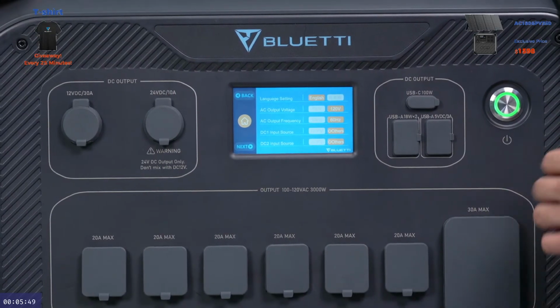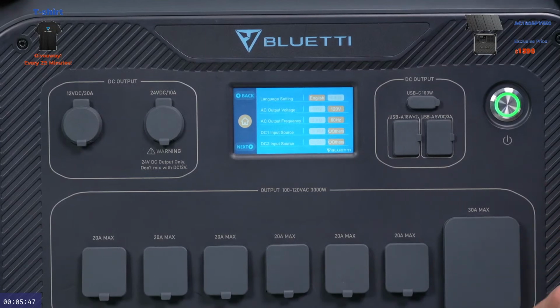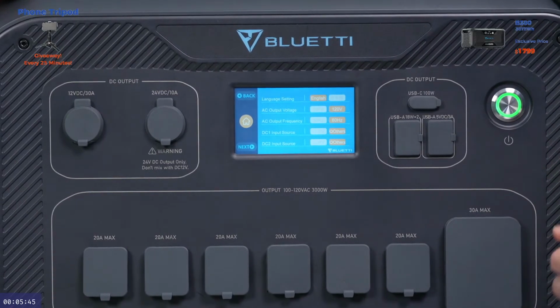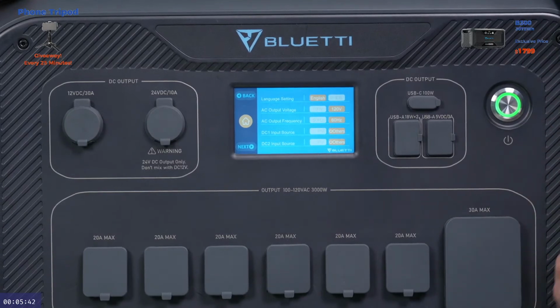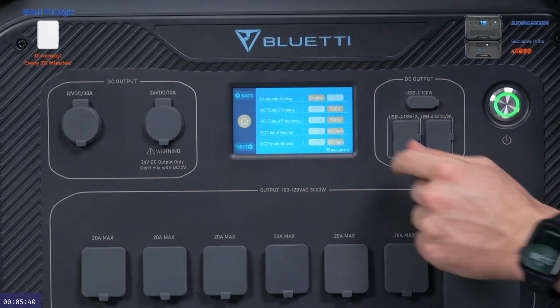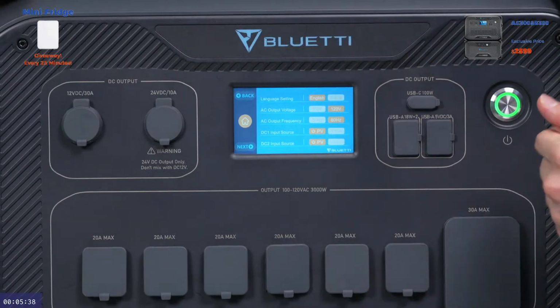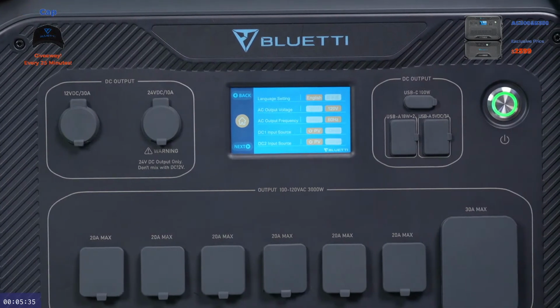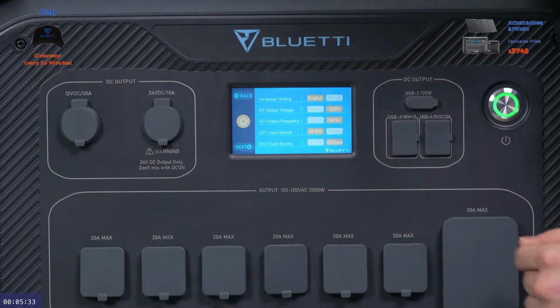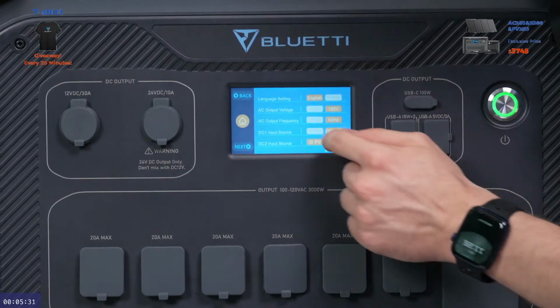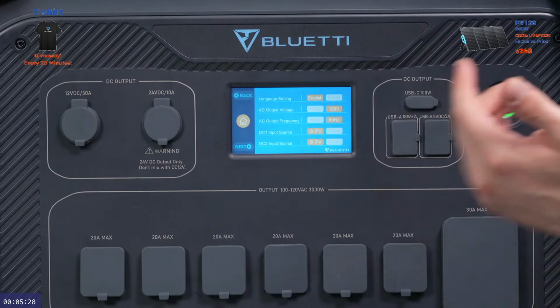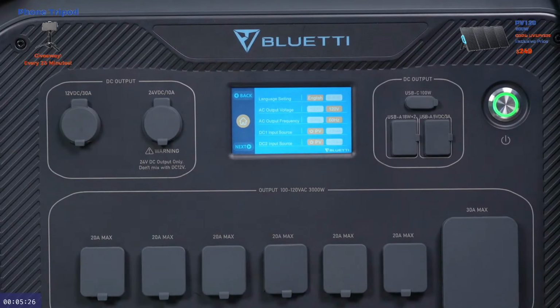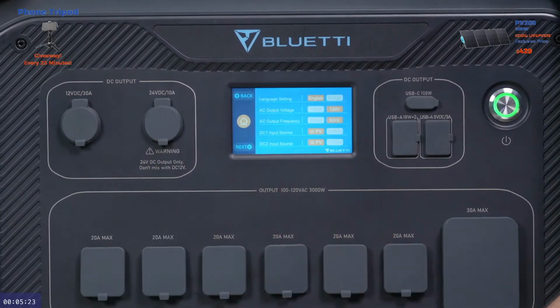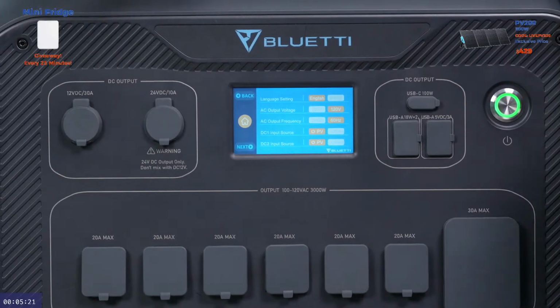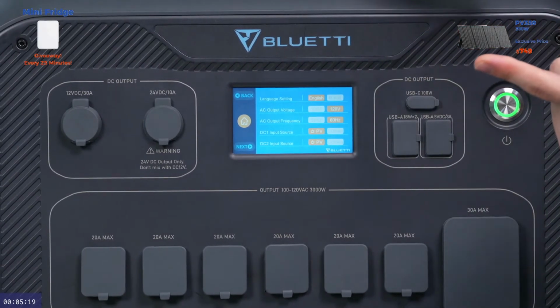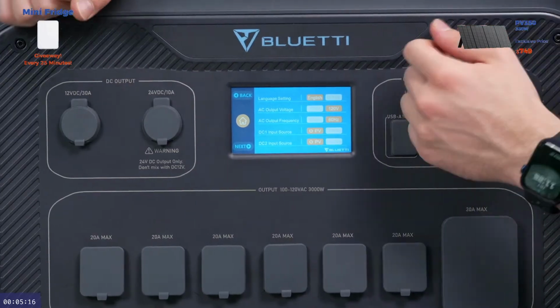Now, what happens if you don't set it to others from PV, and you're indeed charging from other methods, not from PV? The system will give you an alarm - this is it. So just remember to set it to PV or others. As a matter of fact, one of them can be set to PV, the other to others, or vice versa, depending on your situation. When you're charging from literal solar panels, set it to PV. And if you're charging from lead-acid batteries or a car, for example, set it to others.